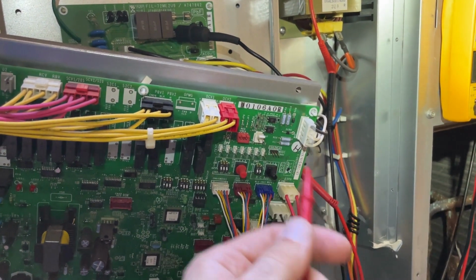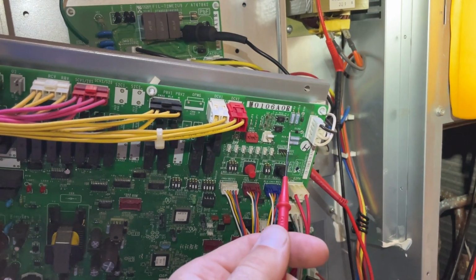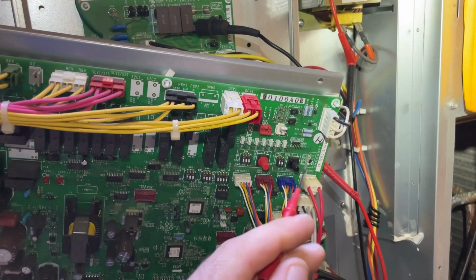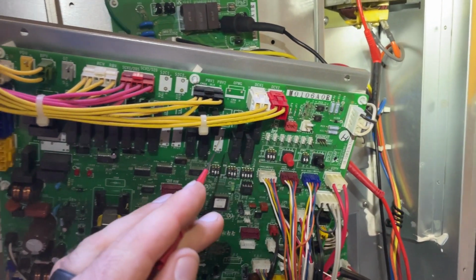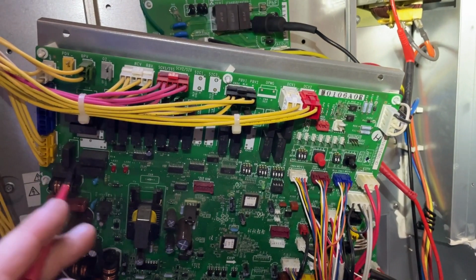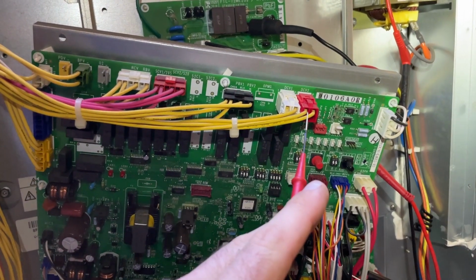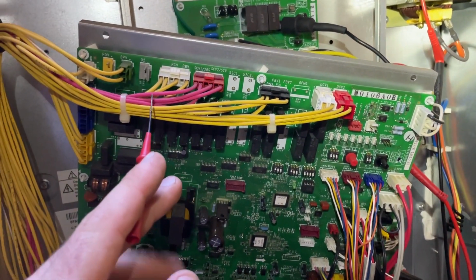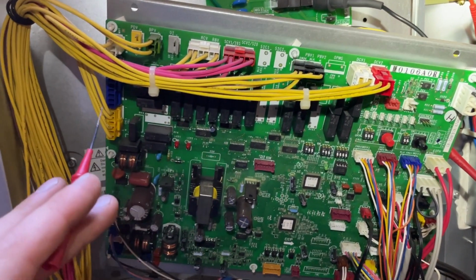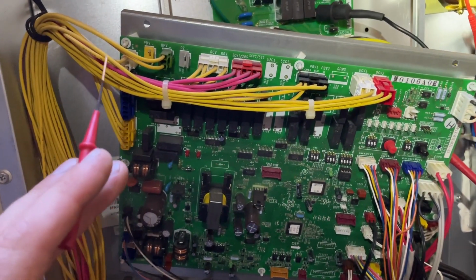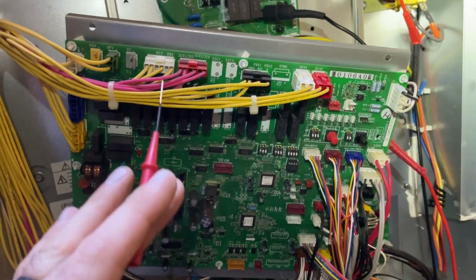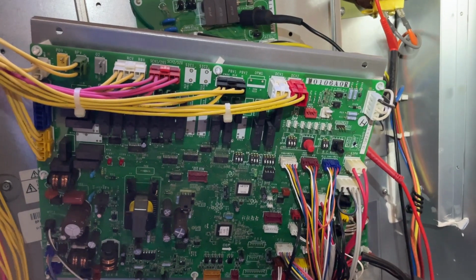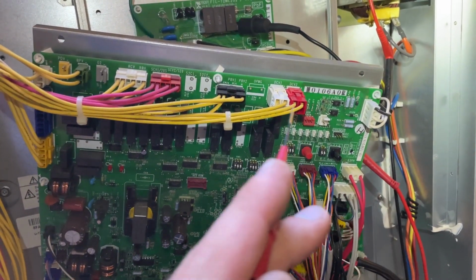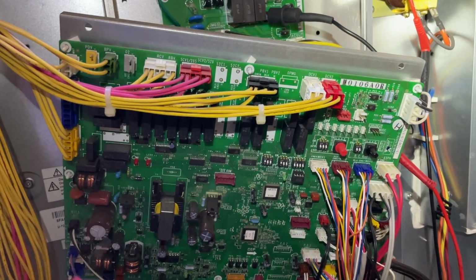I have mains coming in here, and it's most likely feeding these relays, which in turn switch on what are most likely solenoids. On VRF units, all the solenoids and stuff are high voltage, so I need to go down all of these and make sure I've got no shorts to ground.